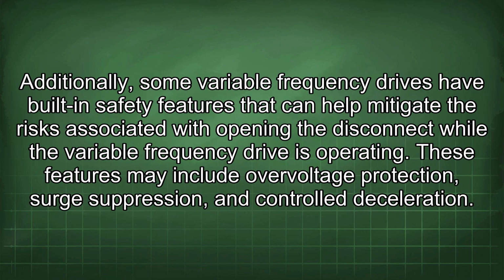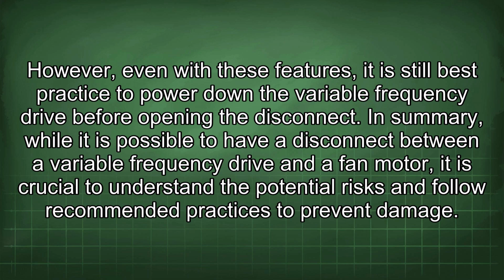Additionally, some variable frequency drives have built-in safety features that can help mitigate the risks associated with opening the disconnect while the variable frequency drive is operating. These features may include overvoltage protection, surge suppression, and controlled deceleration. However, even with these features, it is still best practice to power down the variable frequency drive before opening the disconnect. In summary, while it is possible to have a disconnect between a variable frequency drive and a fan motor, it is crucial to understand the potential risks and follow recommended practices to prevent damage.